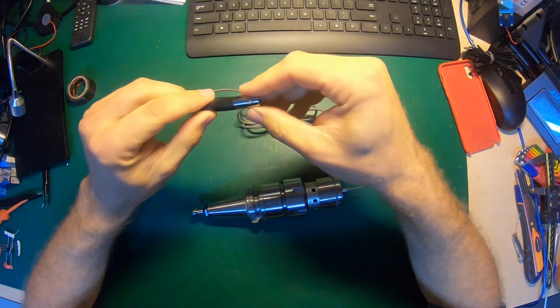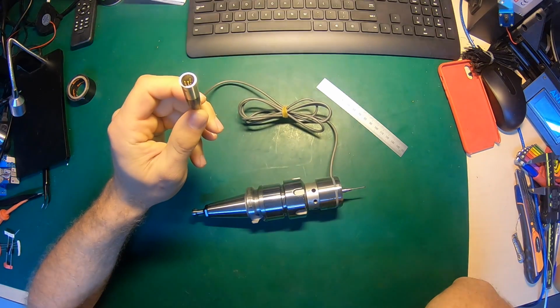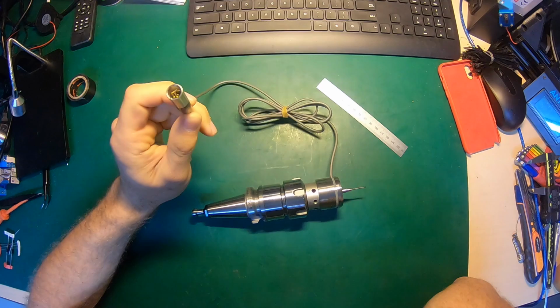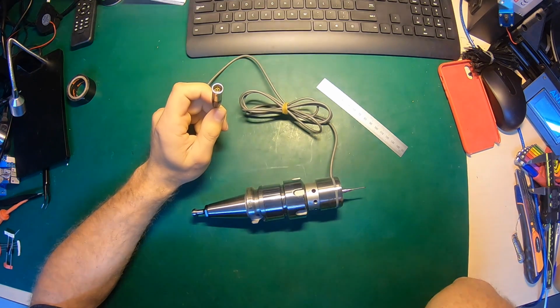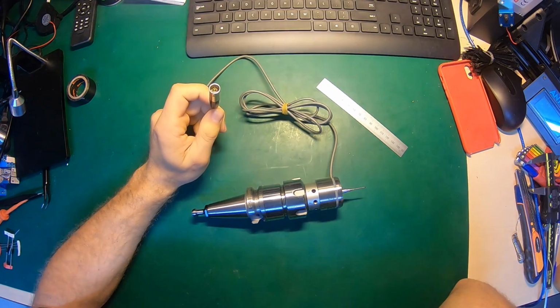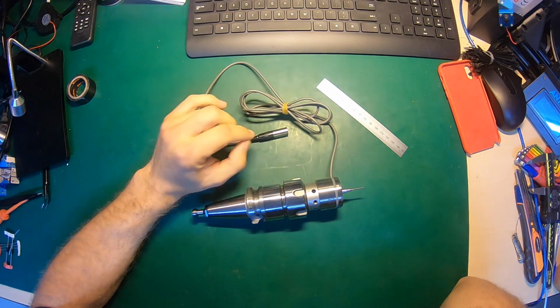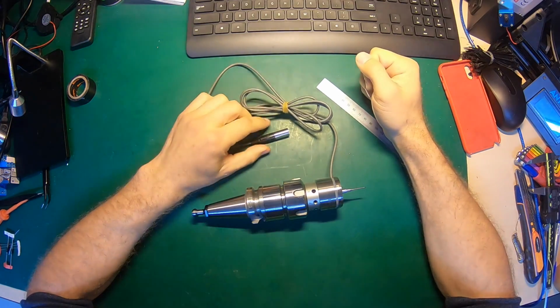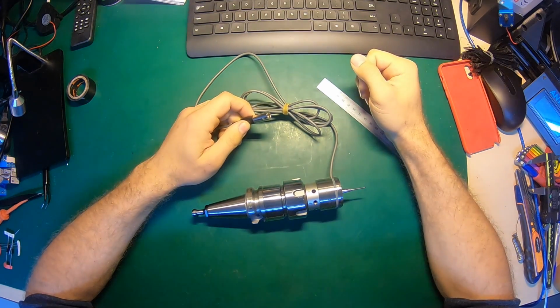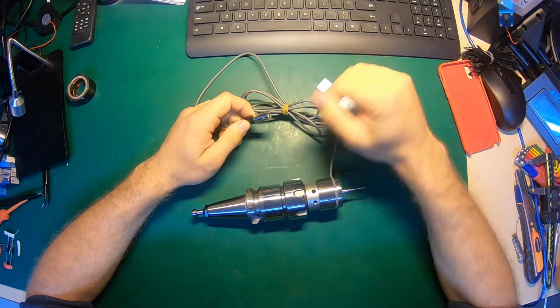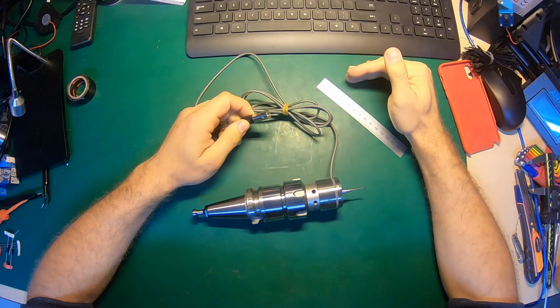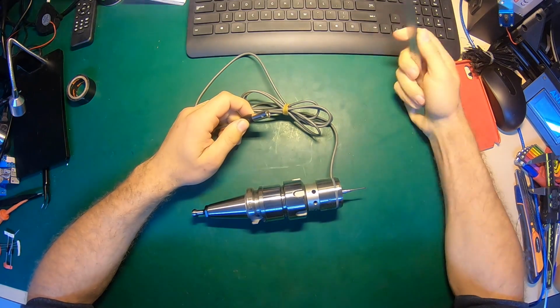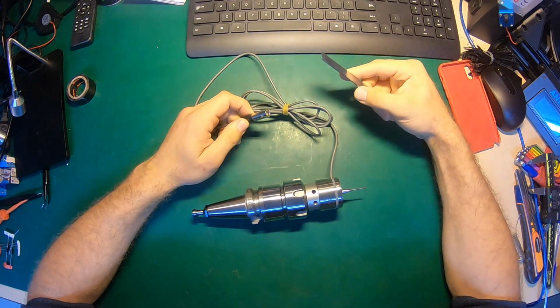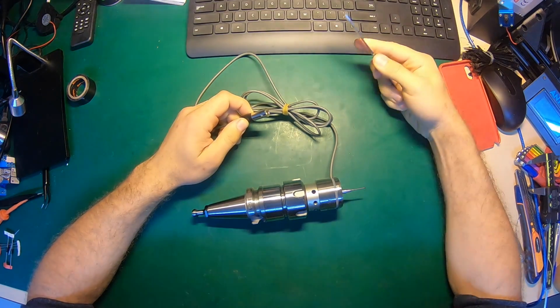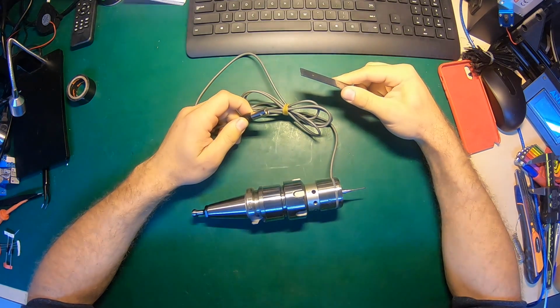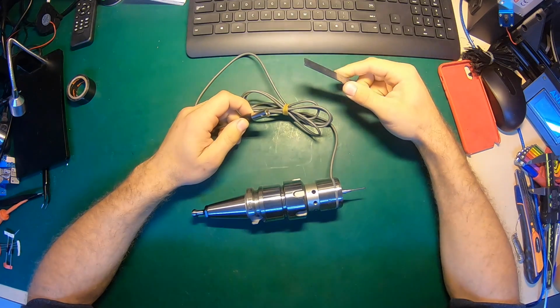One very important aspect is that the way I did this wiring is because my controller has PNP inputs. There are two types of inputs, PNP and NPN. If you don't want to do this wiring, you can avoid it by buying the hot plug interface, which adds an extra layer of protection to your sensor. Also, if you have other sensors that are PNP or NPN, you can just connect those to that hot plug interface, and it would work with both PNP and NPN inputs.